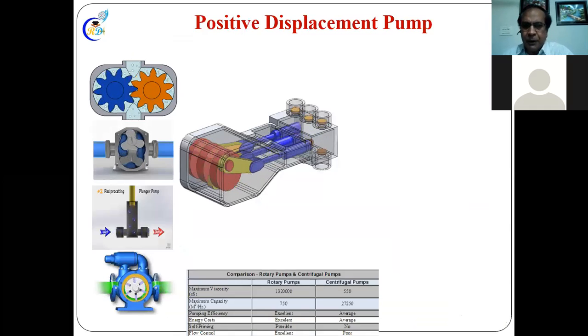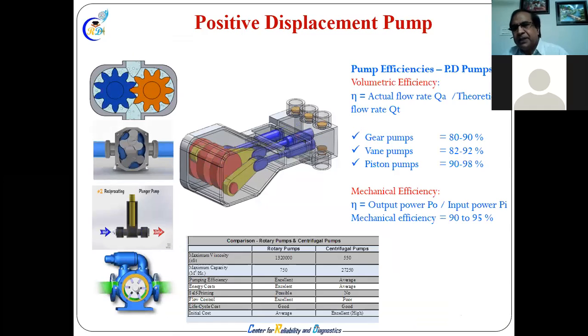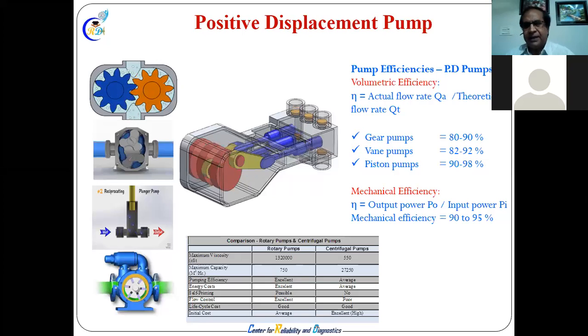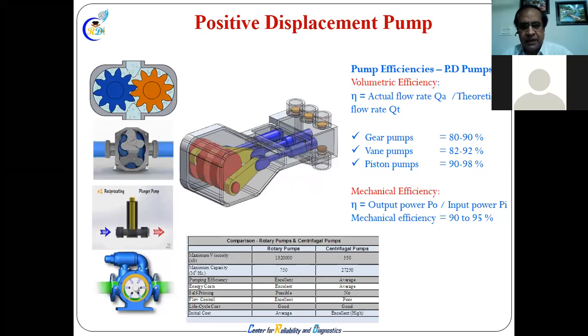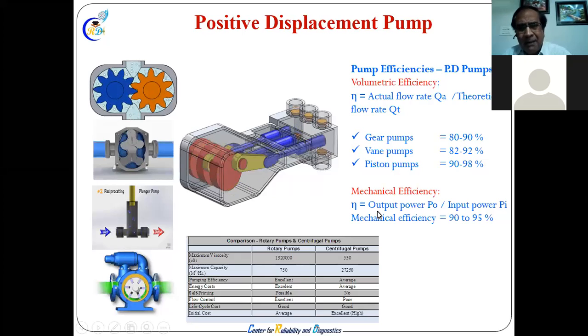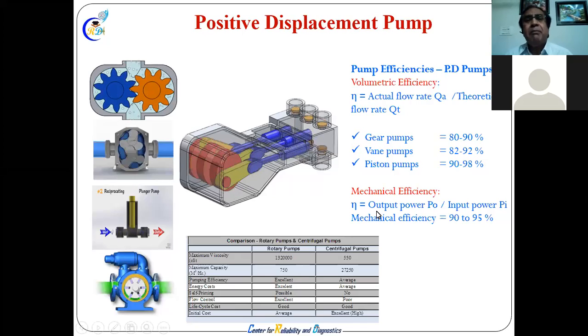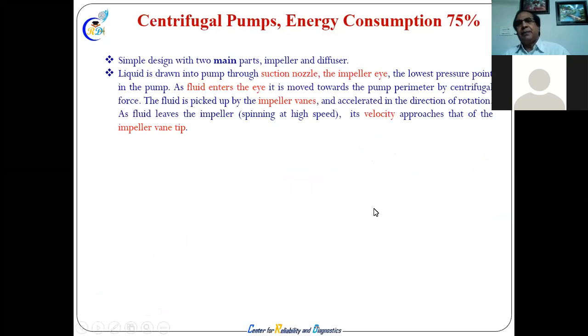Okay, so in positive displacement pumps, if you see, efficiency of the PD pumps is around 98%. Mechanical efficiency 90-95%. This mechanical efficiency can be increased 1%, 2%, a lot of saving by proper maintenance. So in centrifugal pumps, energy consumption itself is 75%. So why are people talking more about reliability and maintenance issues on centrifugal pumps? And here the main issue is pump impeller, nozzle, impeller eye. These are the 2-3 parts that should be taken into account in maintenance.